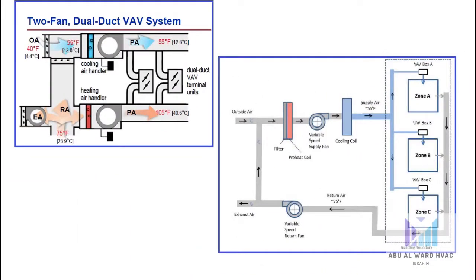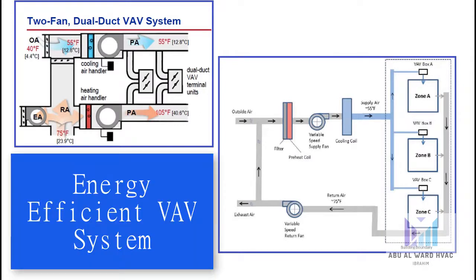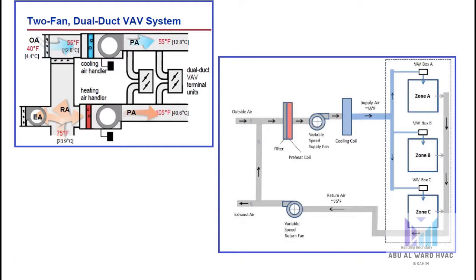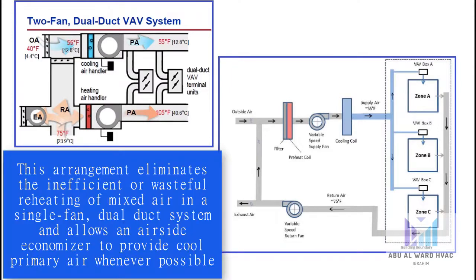This is the second configuration: the two fan dual duct VAV system. Dual duct systems can be very energy efficient when the mixing of cool and heated air is avoided and two supply fans are used — one for heating and the other for cooling. This arrangement eliminates the inefficient reheating of mixed air found in a single fan dual duct system.